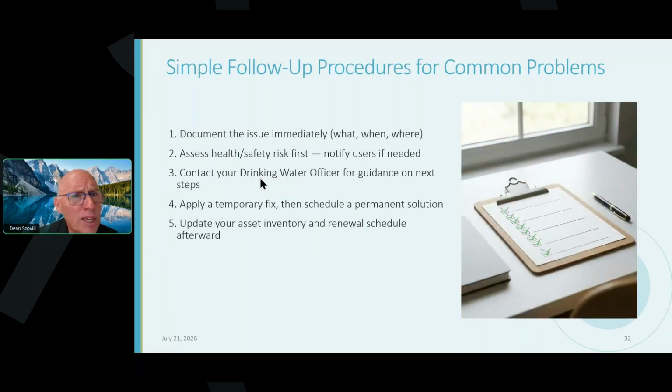For common problems, document the issues immediately: what, where, when. As I mentioned, your reservoir is aging out, it's leaking, the hatch doesn't secure tightly, and we've got intrusion of surface contamination into my reservoir. I mean, if you look around, and I used to say this when I was out in the community doing field work, you can see that there's a lot of wildlife out here, and birds are considered wildlife. What do birds do? They walk all over your reservoir, right? And they poop, and guess what's in their poop? I have a background in public health, so all birds carry salmonella in their digestive tract.